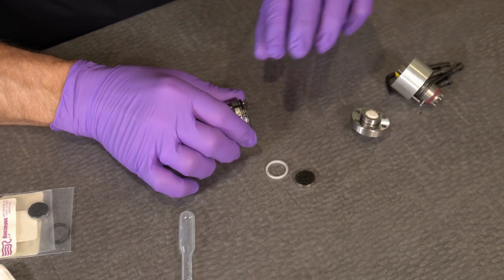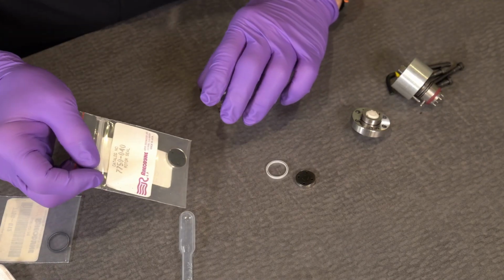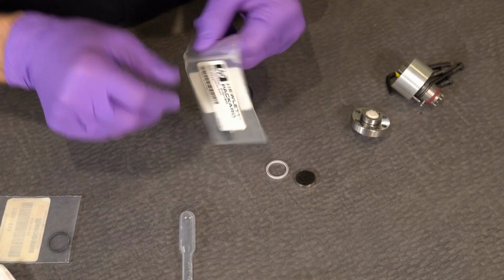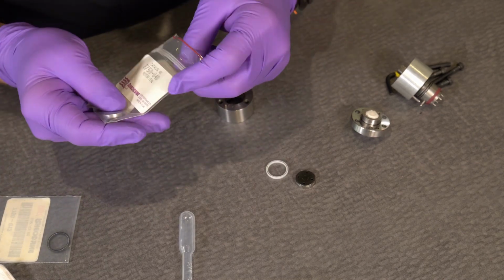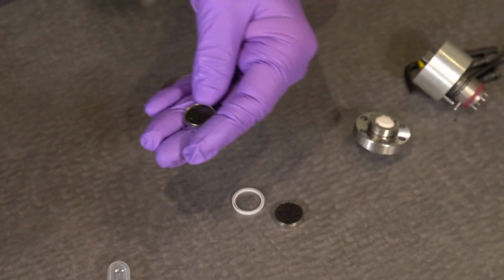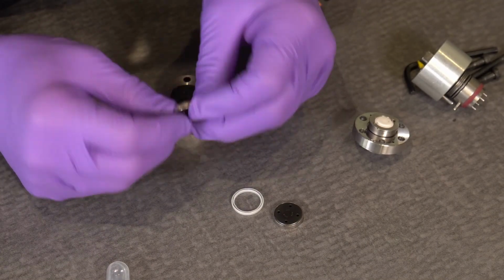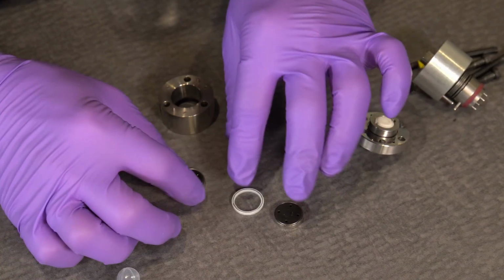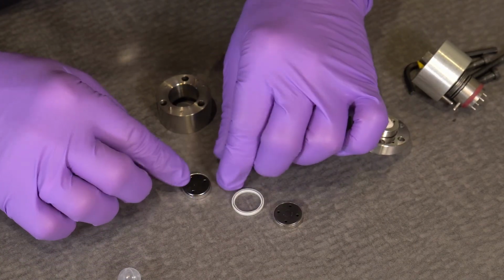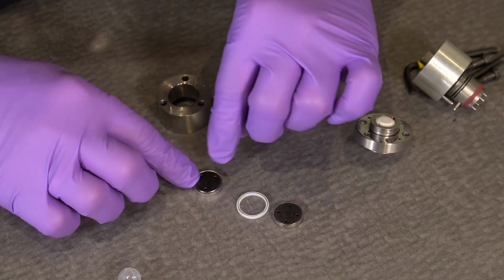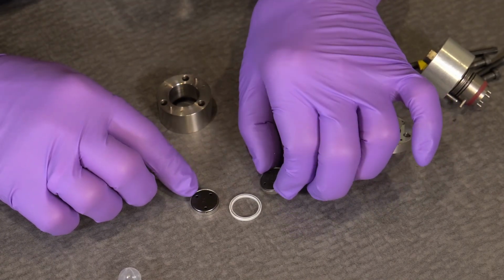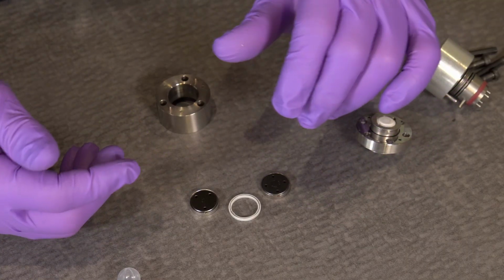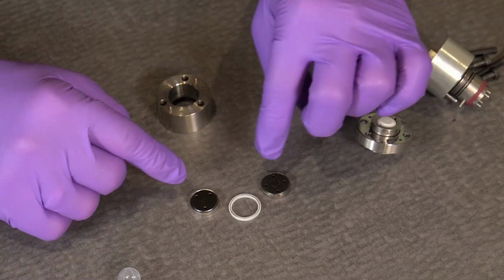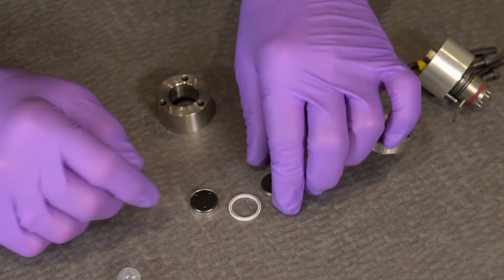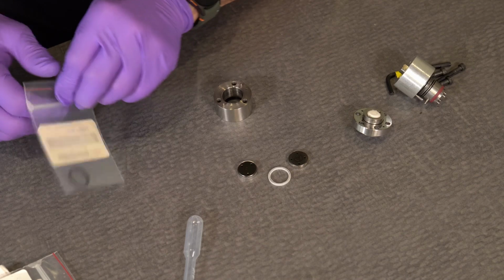We replace them with brand new Rheodyne parts. Oh my gosh, that's an old one. It still says Hewlett Packard on it. So you get the Rheodyne part, and you make sure you get the right rotor seal for your particular injection valve. The one I showed you that just came out of the package has 2 little ports. The one that was already in there has 3 little ports. The difference between a common injection valve and a switching valve is just the number of little connections on the inside.